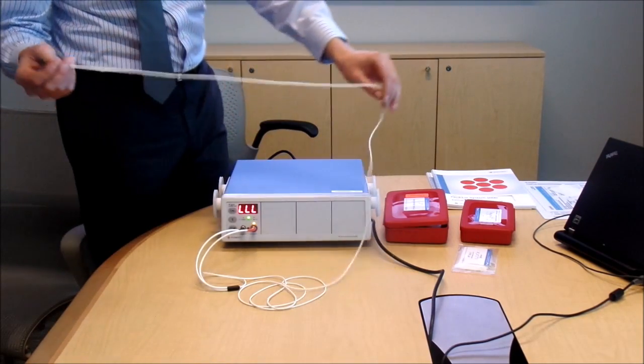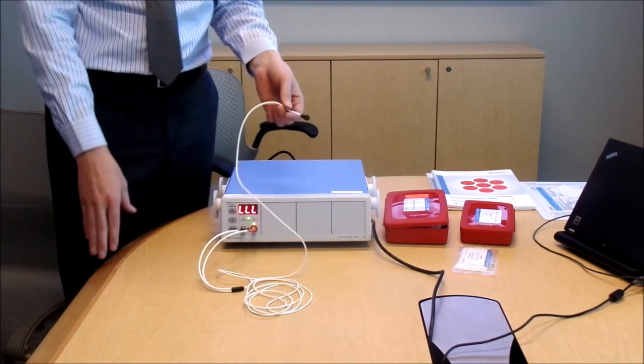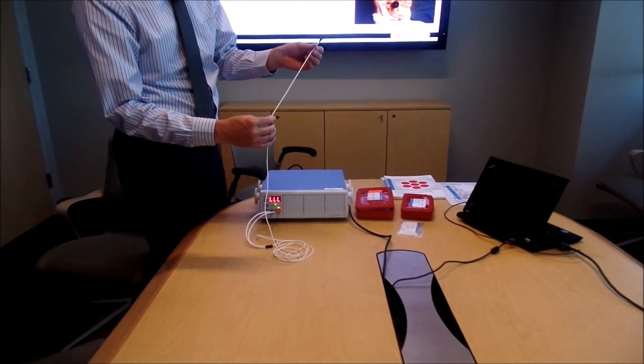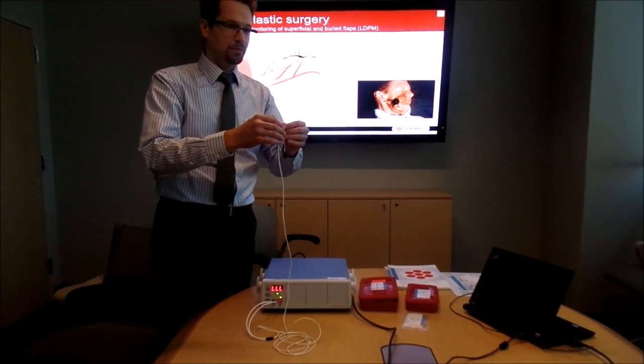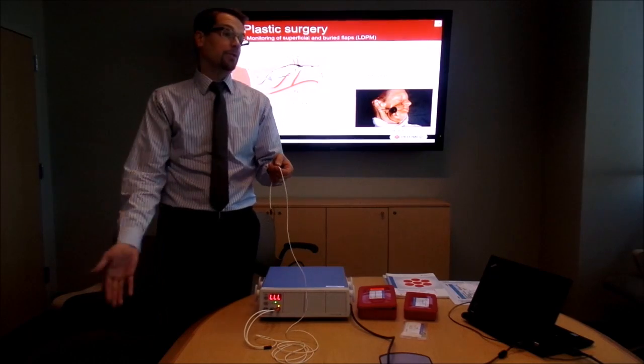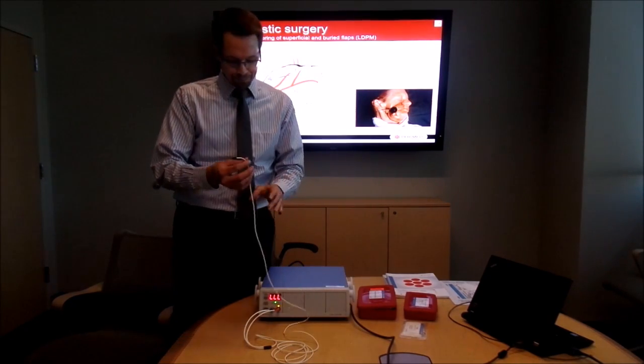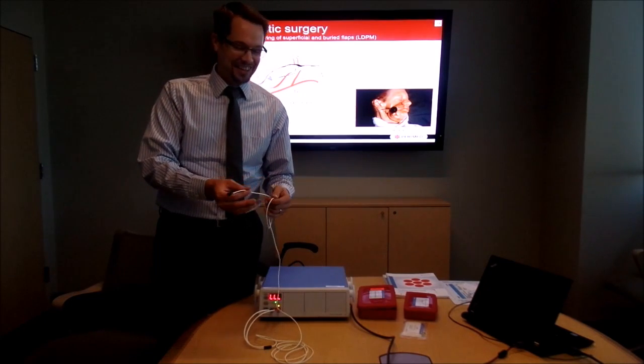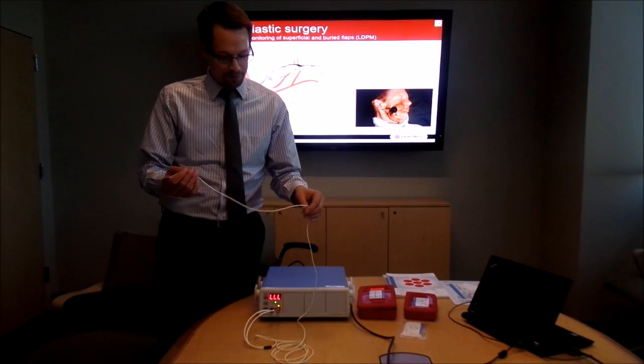Now this probe has not yet been calibrated, but the probe itself can certainly be sterilized. The gas sterilization or a sterrad type sterilization method is preferred to ensure longevity of the probe itself. And being that the probe is basically built up of optical fibers, it will be sensitive to kinking, bending the cable sharply, and also crushing damage, as if the cable comes down on the ground potentially and somebody rolls it over with a cart or something else, that might be all it takes to damage the probe. In some cases, we might be able to repair a damaged probe, so please don't throw it out if something goes wrong, but contact us and we'll see what we can do to at least troubleshoot and see if there's a way to bring it back to life.